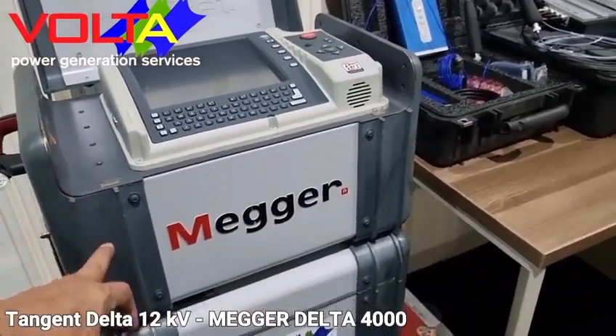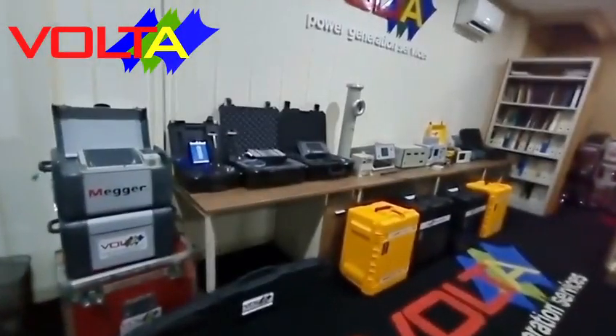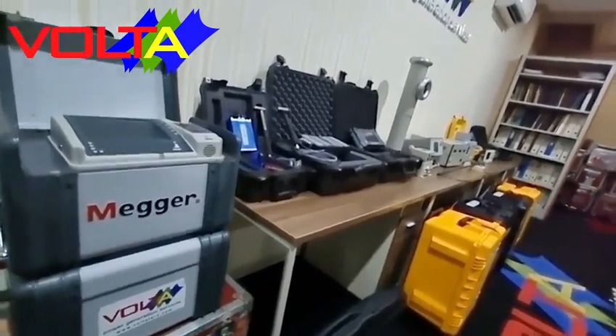The second tangent delta instrument is the Megger Delta 4000 series, able to test tangent delta up to 12 kilovolts. Equipped with a resonant circuit, the instrument is able to test generators with insulation capacitance up to 1.2 microfarad at 10 kilovolts.